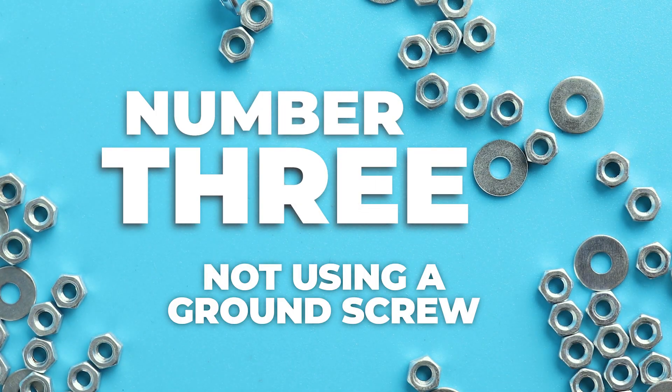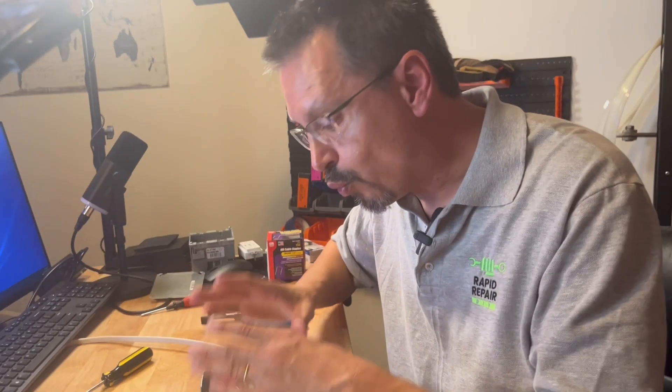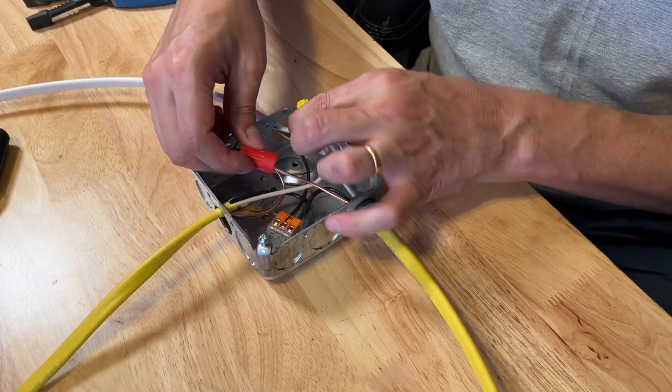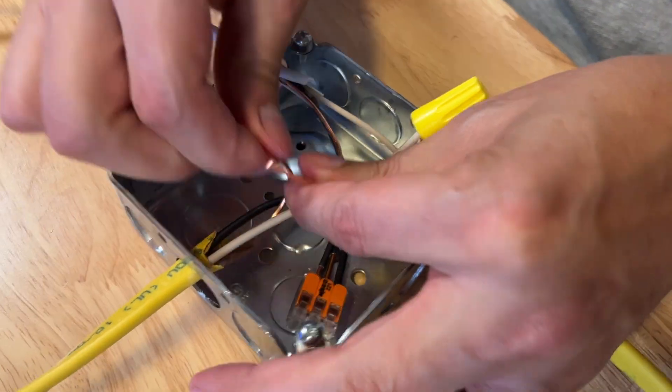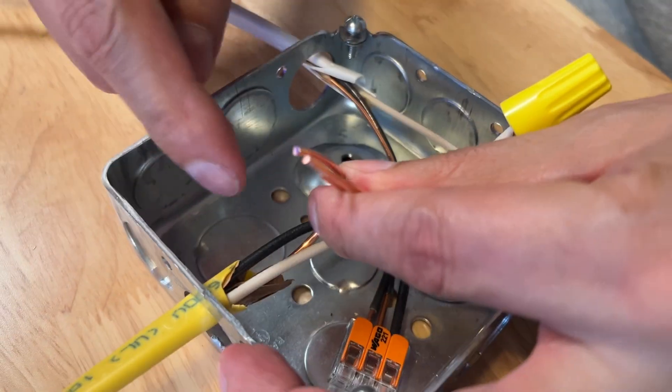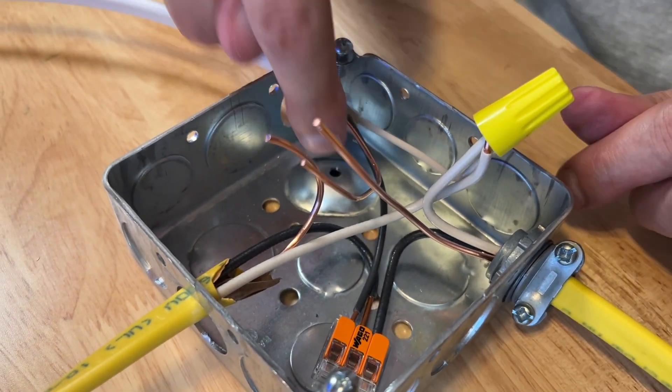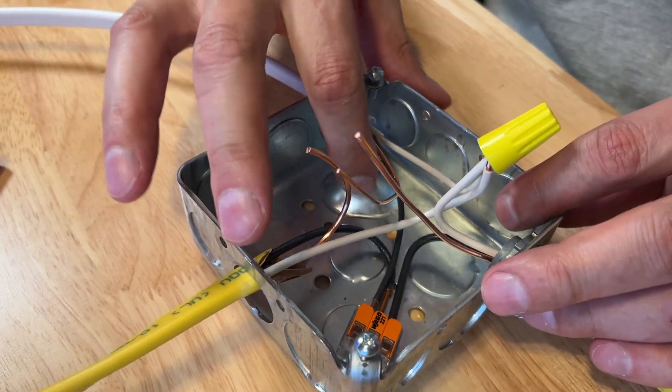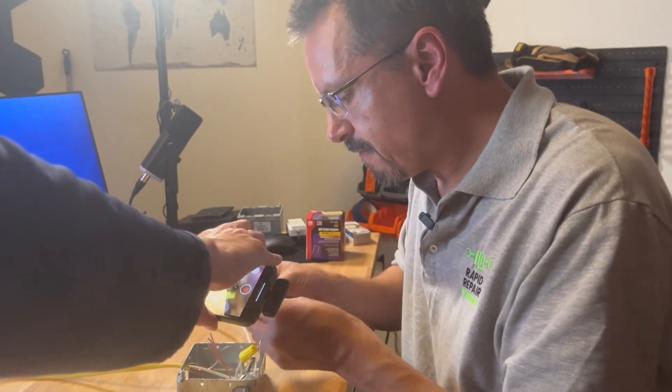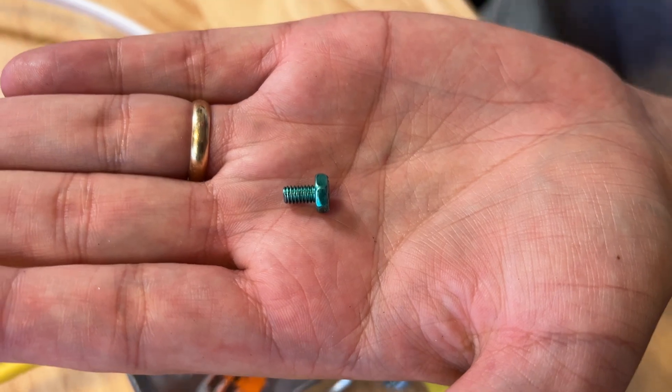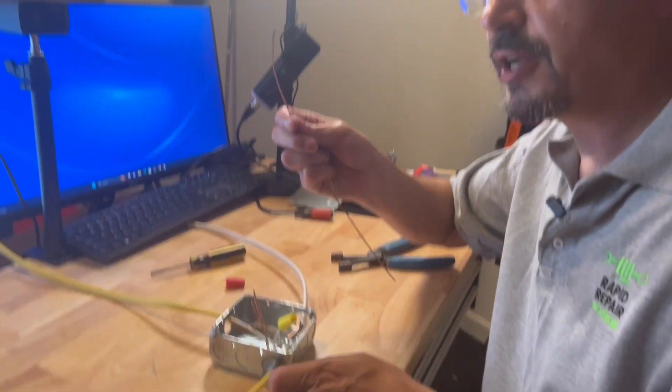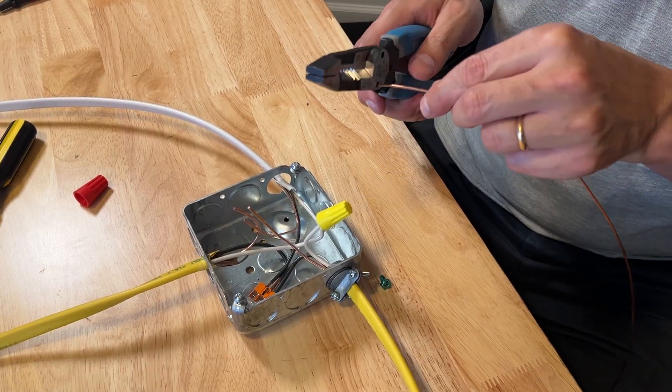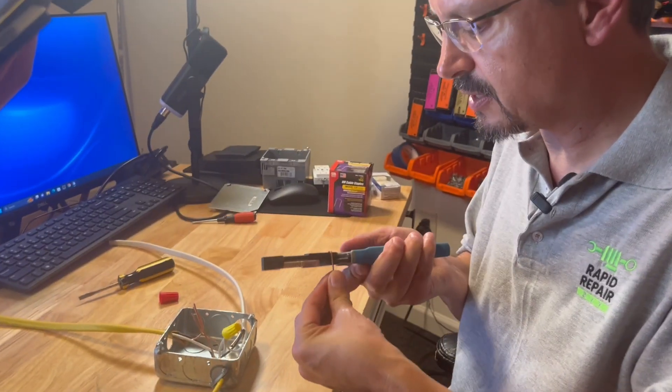Number three, not using a ground screw. So with metal boxes, you have to ground it to the box. Now here we have the grounds all bonded together. And that's great. However, you are required to have it bonded to the metal box. Now on this metal box, it gives you that funny little bump out shape. That bump out is for a grounding screw. So what you're going to do is you're going to get bare copper wire, and you can just cut it out of your existing Romex. Use your wire cutter to put a little twist on there.